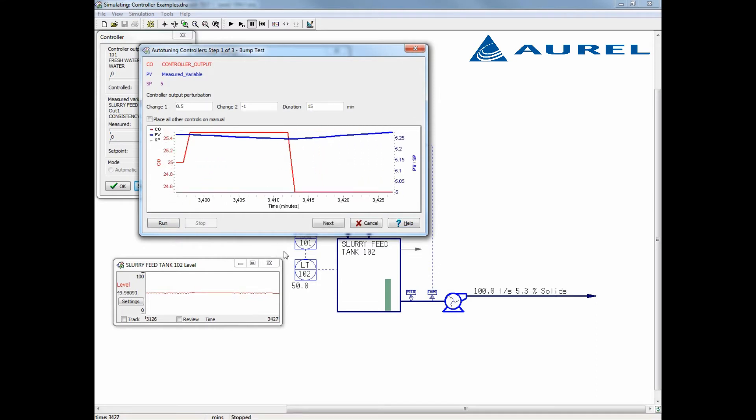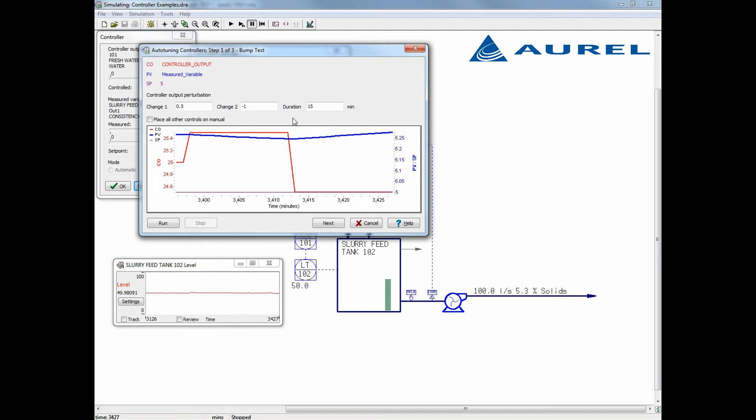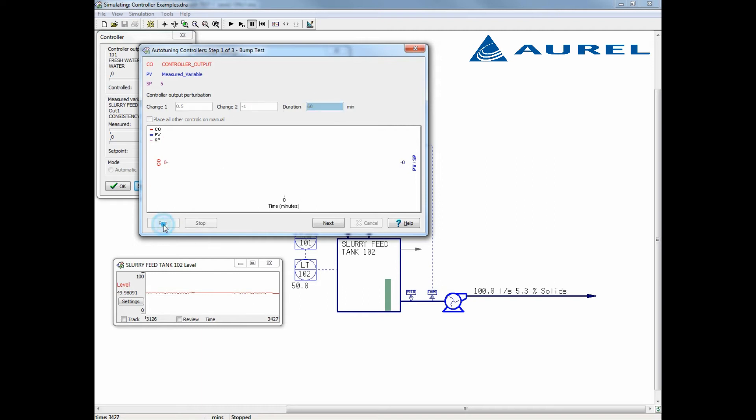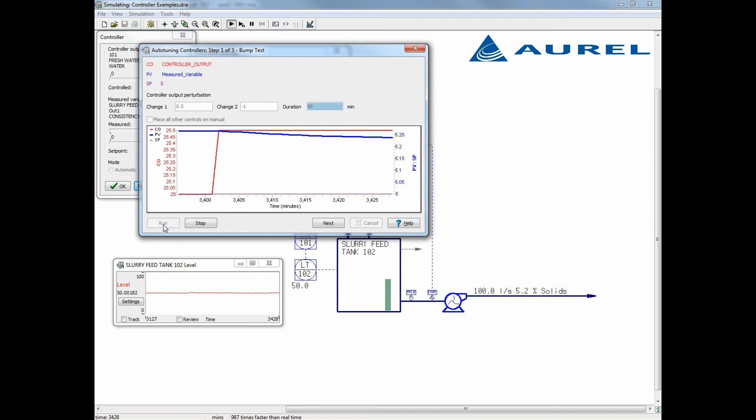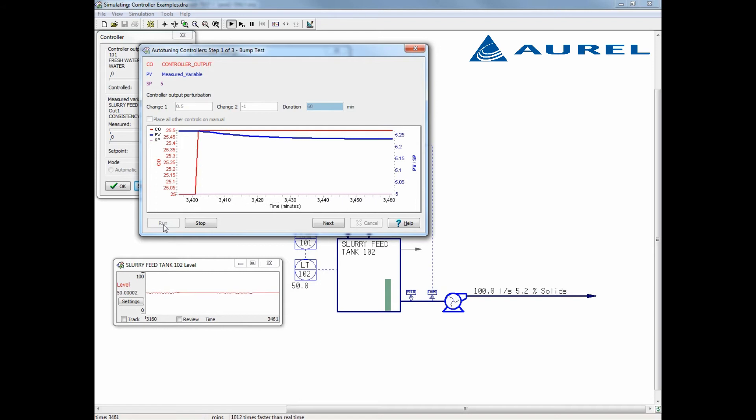We know this should be a self-regulating controller, that is, the system will settle in to a new set point after a period of time. However, we notice this model appears to be similar to the integrating controller we saw previously. This occurred because the bump test does not have enough time between changes to let the system settle in to a new steady state. To account for this, we can change the duration from 15 minutes to 60 and run the bump test again.